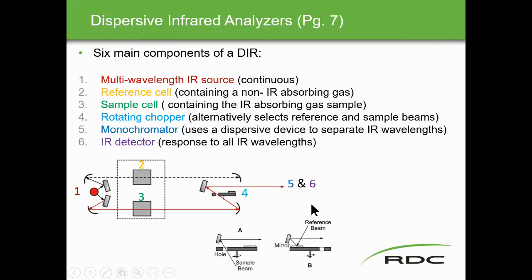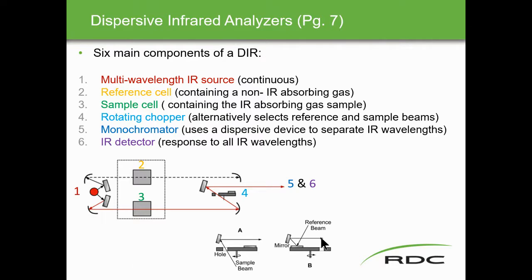The chopper, because it rotates, alternates between the sample cell and the reference cell. The sample beam goes through at one position, and as it spins to the other position, the reference beam is directed via a mirror. The analyzer receives alternating reference and sample signals — reference, sample, reference, sample — which prevents drift.